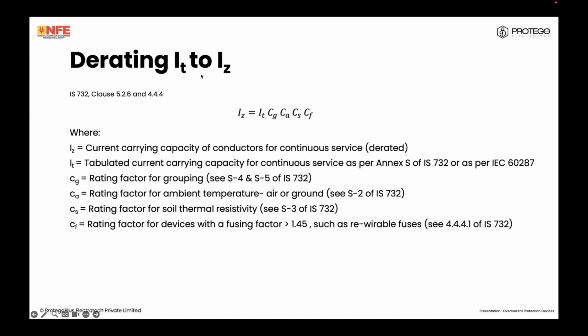Derating factors in IS 732 and NEC are recognized as four. There is a rating factor for grouping: how many cables are bunched together, how many circuits are bunched together, which will affect the ability to dissipate heat. You'll find this information in Annex S4 and S5 of IS 732. This is an Annex S, by the way.